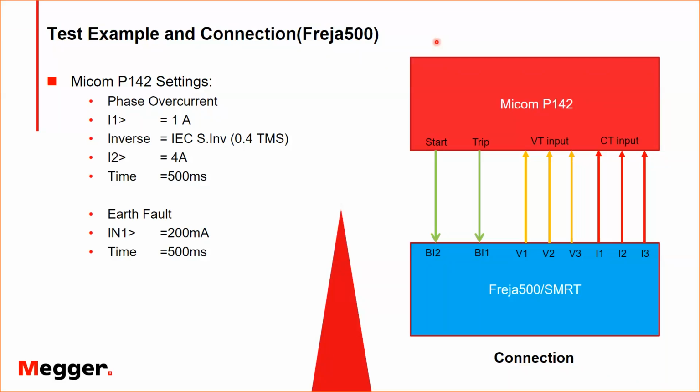protection. Having a dedicated earth fault CT makes the application much more secure than using a calculated one. Or for the calculated one, maybe you need to, I would say, increase the setting compared to an actual measured fourth current input.